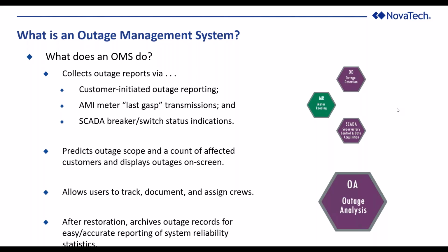There are more automated systems, where a customer calls into a number and reports it more automatically, including the solution the industry calls IVR, or Interactive Voice Response. If you have an AMI system, those meters may have a small battery or capacitor so that if the meter ever loses its source, it has just enough power to send a transmission we call a last gasp, notifying that the meter lost its source. That's fairly useful for indicating meters that have lost power.